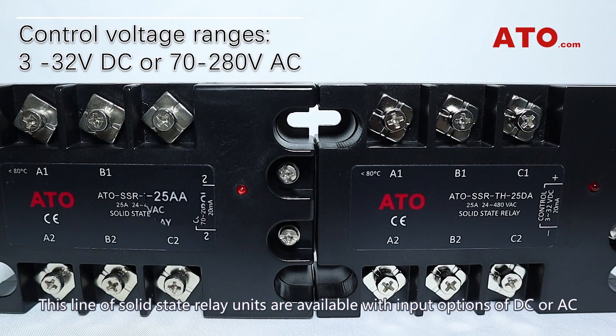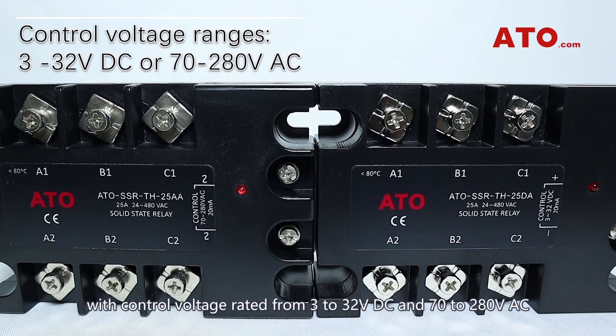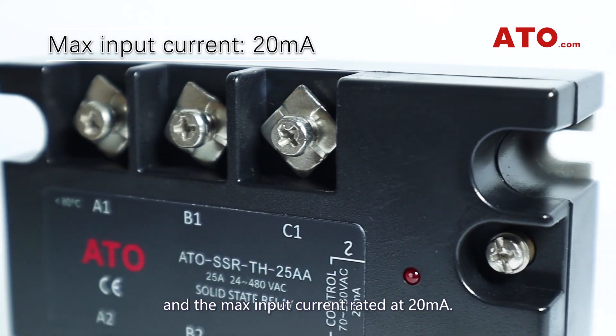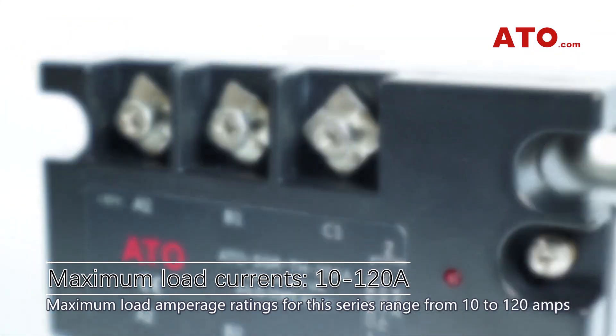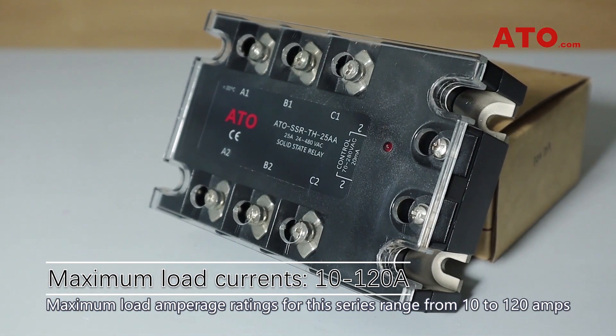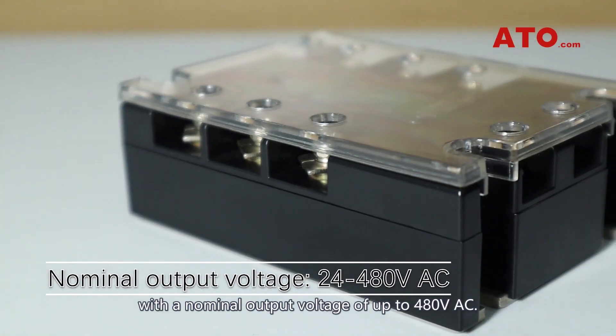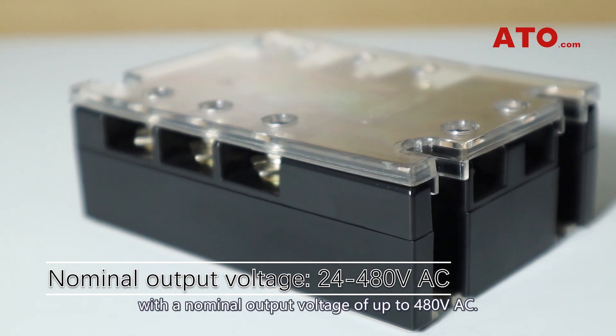This line of solid-state relay units are available with input options of DC or AC, with control voltage rated from 3-32V DC and 70-280V AC, and the max input current rated at 20mA. Maximum load amperage ratings for this series range from 10 to 120A, with a nominal output voltage of up to 480V AC.